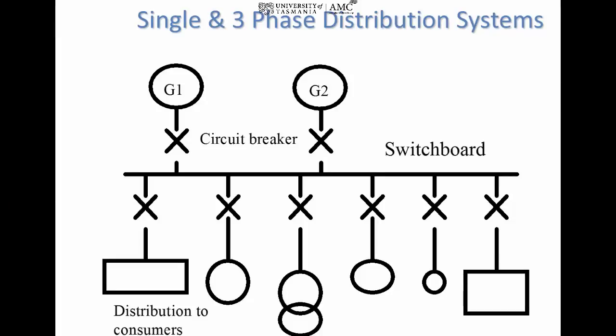Let's talk about our distribution systems. So we're talking about our main switchboard and our distribution boards. We have our generator 1 and generator 2. We can call them alternators, alternator 1 and alternator 2, or genset 1, genset 2, all same thing, different smell. Okay, so this is powering what we traditionally would call our bus bar. In the early days I called them buzz bars because of the electron flow through there. They would kind of buzz, and they called them bus bars, which in a lot of systems are a live big copper bar, and often they're uninsulated, which allows for heat distribution or dissipation within the switchboard.